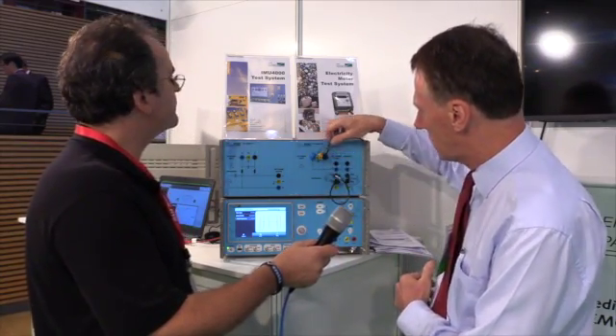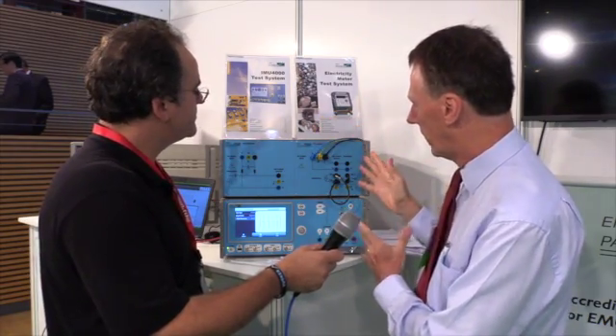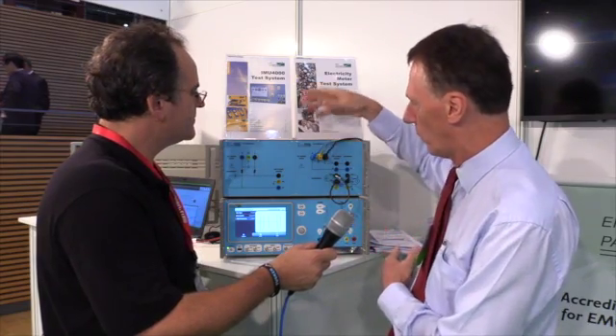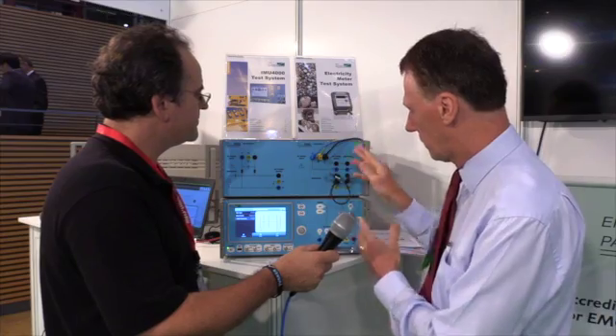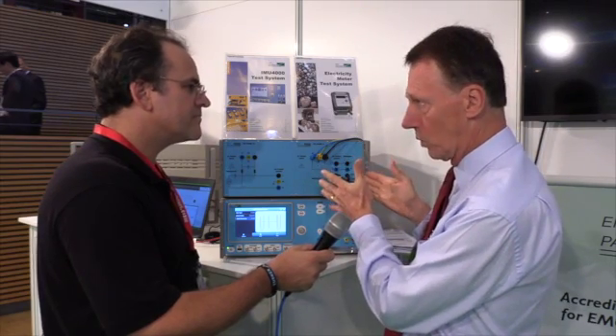The device itself has to have a voltage source. Normally an electricity meter has two coils, a current and a voltage coil. The voltage coil can be fed directly from the power main, as I have here, or from a stable AC supply. And the current coils have to be connected to the smart extension as well. Just for demonstration purposes, I've made a short circuit on the output. Because built into this unit, we have a current source.